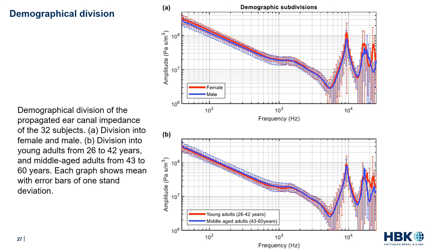Next, the 32 propagated impedance measurements are demographically divided into female and male groups, and for each group the mean and standard deviation are calculated, shown in graph A. Similarly, a demographic division into two age groups — young adults from 26 to 42 years and middle-aged adults from 43 to 60 years — is shown in graph B. The mean of the female group is within one standard deviation of the male group and vice versa. The mean of the young adult group is within one standard deviation of the middle-aged group and vice versa. Therefore, no statistically significant difference in ear canal impedance between female and male, or between young and middle-aged adults, can be concluded based on the 32 subjects. However, a slight tendency of higher impedance can be observed for females as well as for middle-aged adults at lower frequencies.